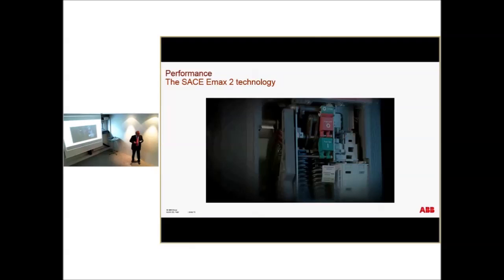Four coils, because reducing the space, you have now, everybody has 3 coils, but in this case, you can have 4 coils, 2 double closing or 2 double opening. You have a redundancy again on the coils. So we said before we have redundancy on the measurement, we have redundancy on a lot of things like communications. We want to make redundancy also on this one, redundancy on the heating. So we try to prevent all possible unsafe situations.